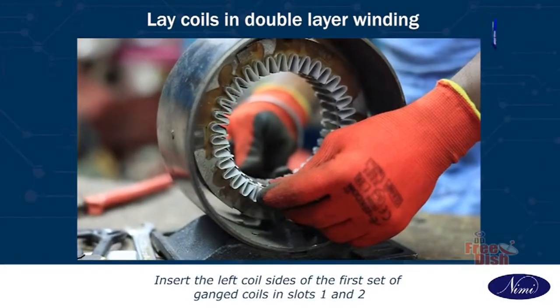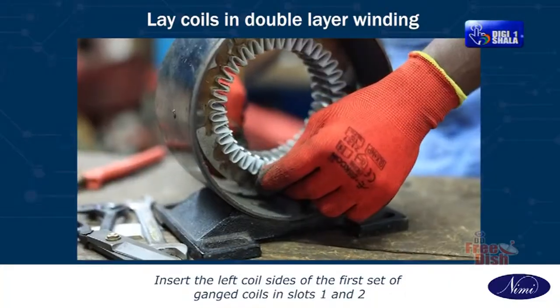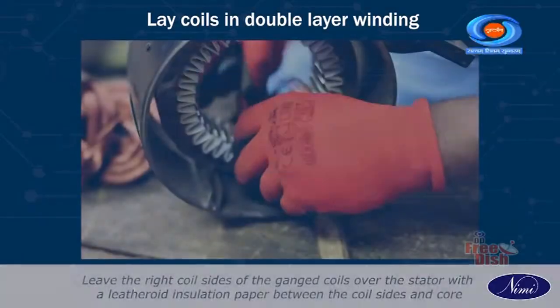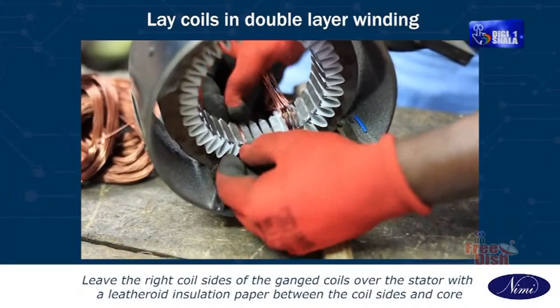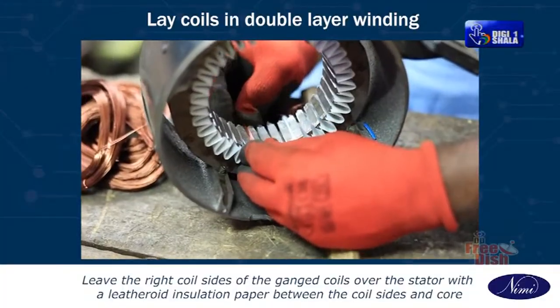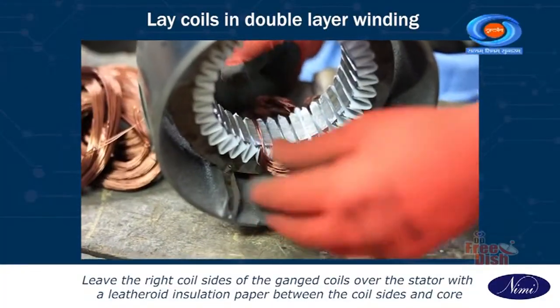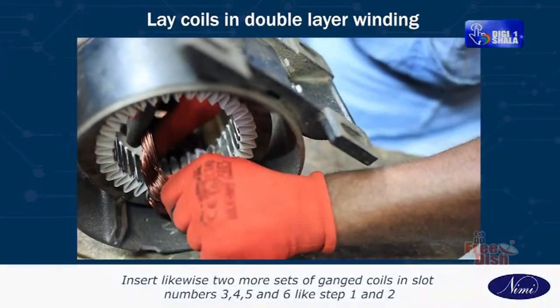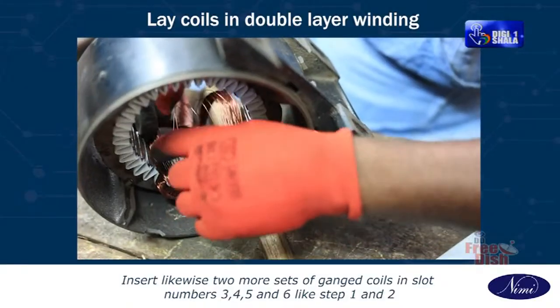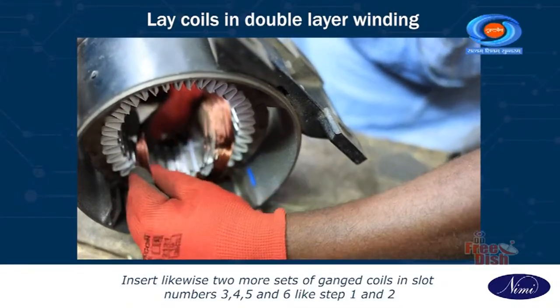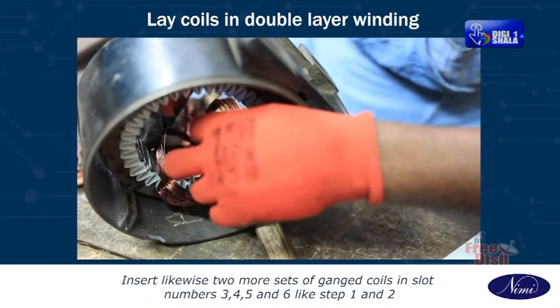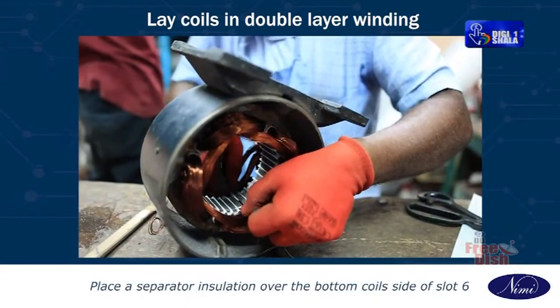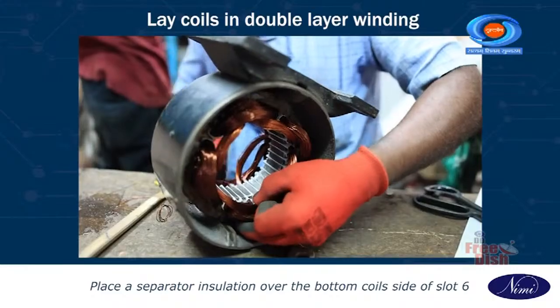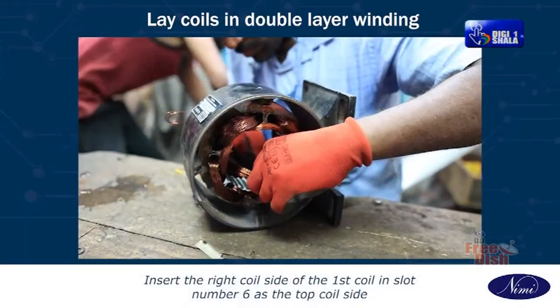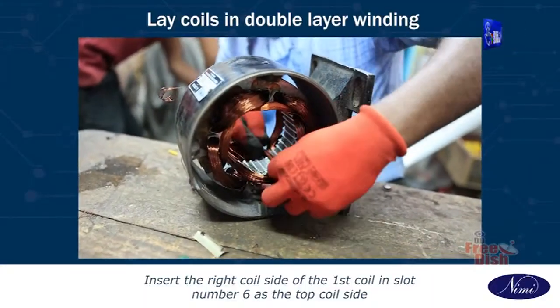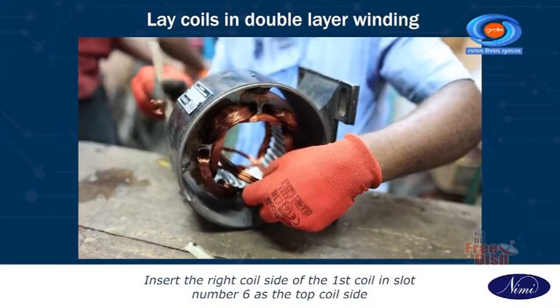Insert the left coil sides of the first set of ganged coils in slots 1 and 2. Leave the right coil sides of the ganged coils over the stator with the leatheroid insulation paper between the coil sides and core. Insert likewise two more sets of ganged coils in slot numbers 3, 4, 5 and 6 like steps 1 and 2. Place a separator insulation over the bottom coil side of slot 6. Insert the right coil side of the first coil in slot number 6 as the top coil side.